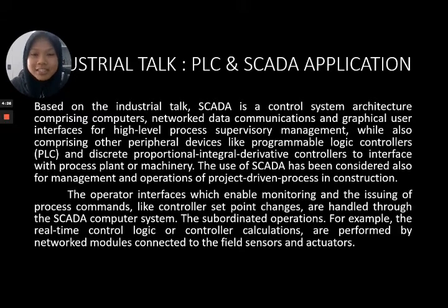Based on the industrial talk, SCADA is a control system architecture comprising computers, network data communication, and a graphical user interface for high-level process supervisory management, while also comprising other peripheral devices like programmable logic controllers, which is PLC, and discrete proportional integral derivative controllers to interface with process plant or machinery. The use of SCADA has also been considered for management and operation of project-driven processes in construction. The operator interface, which enables monitoring and the issuing of process commands like controller set point changes, is handled through the SCADA computer system.